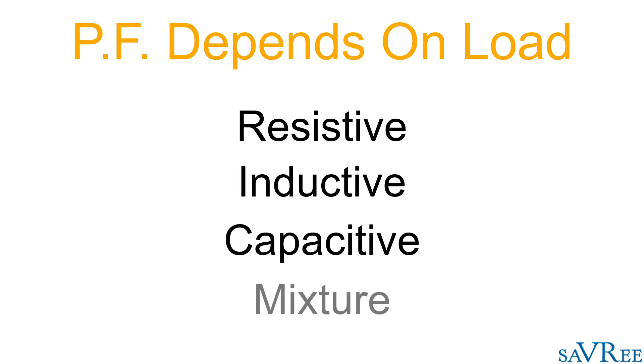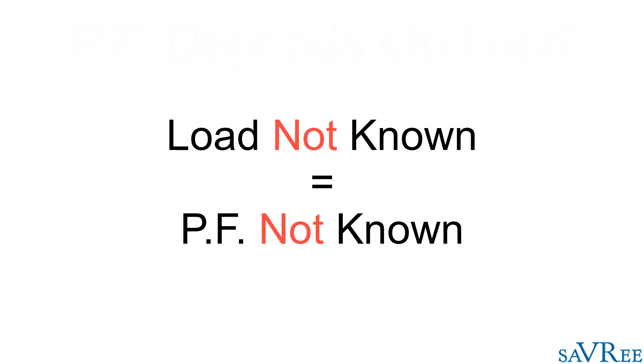The power factor is defined by the type of load connected to the transformer or generator. Loads are either resistive, inductive, capacitive, or a mixture of these. Because transformer and generator manufacturers do not know the load to which the generator or transformer will be connected, it is not possible for them to define the power factor.